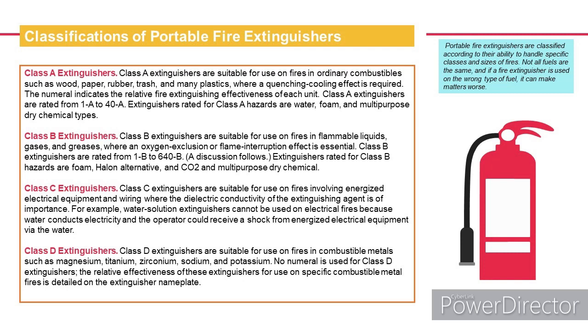Class C extinguishers. Class C extinguishers are suitable for use on fires involving energized electrical equipment and wiring where the dielectric conductivity of the extinguishing agent is of importance. For example, water solution extinguishers cannot be used on electrical fires because water conducts electricity and the operator could receive a shock from energized electrical equipment via the water.